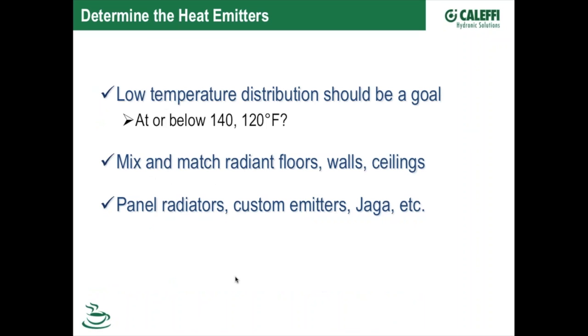So then the next step is, how are we going to get the heat to the space, to the room? What type of heat emitters are we considering? Are they low temperature devices? Are we going to connect those to a high temperature boiler? If so, you're going to want to look at one of our mixing devices. We'll get through some of those today. You can mix and match systems. In fact, in January, Jody's presentation will be talking about how you can come up with multiple temperature supplies off of one system. Sometimes you'll have a high temperature, maybe a coil or something like that in a fan unit, and then you'll have some radiant. So how do I mix multiple temperatures? The whole webinar that Jody will do will be addressing that.